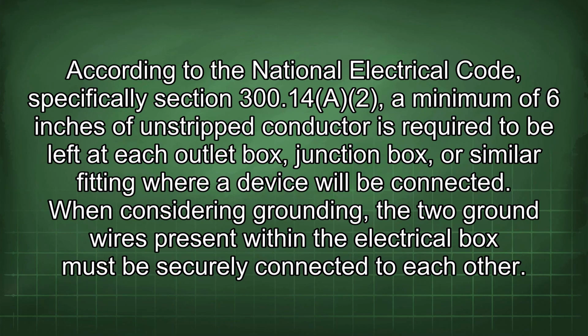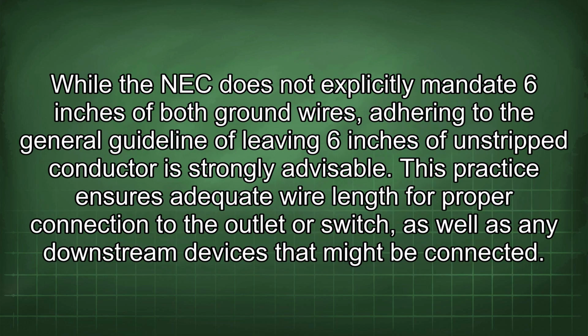According to the National Electrical Code, specifically Section 300.14, a minimum of 6 inches of unstripped conductor is required to be left at each outlet box, junction box, or similar fitting where a device will be connected. When considering grounding, the two ground wires present within the electrical box must be securely connected to each other. While the NEC does not explicitly mandate 6 inches of both ground wires, adhering to the general guideline of leaving 6 inches of unstripped conductor is strongly advisable.